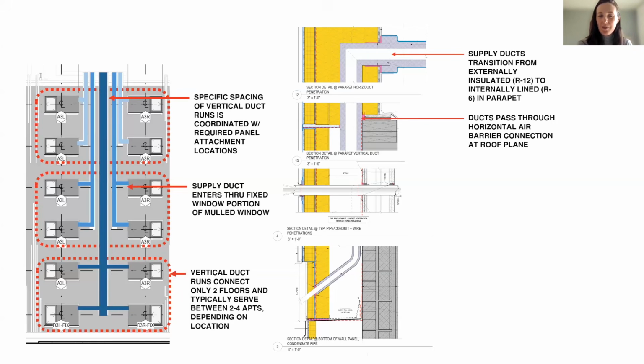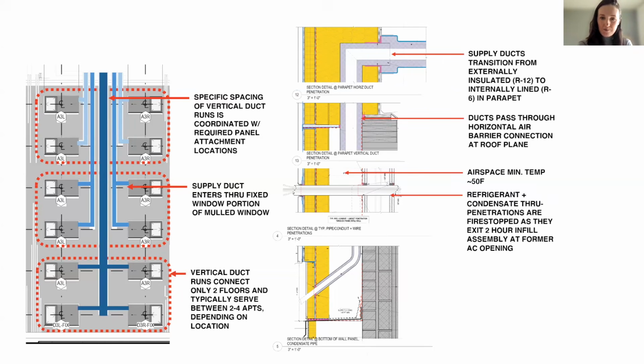So you can see going through the wall section here, here's our duct transitioning from externally insulated to internally lined, passing through our air barrier, which in this case is more or less the plane of the existing roof. We've got a 9-inch gap. Its airspace has a minimum temperature of about 50 degrees. We're going to have to fire stop everything that goes through this 2-hour masonry wall. So it's another challenge. And then at the bottom of every panel, we're leaving off about 16 inches of sheathing to be installed on site so that all of our line sets, our condensate and drainage can come out of the panel and be organized before we go ahead and sheath it and finish it off.